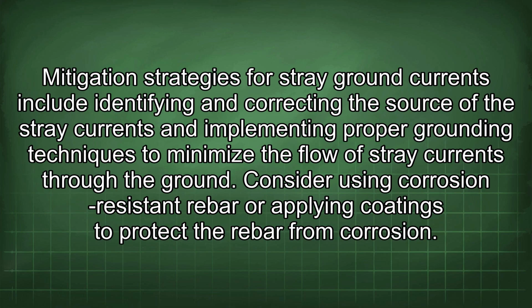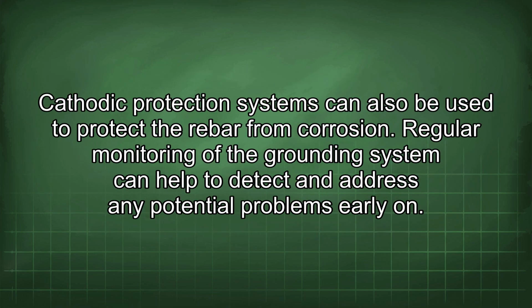Mitigation strategies for stray ground currents include identifying and correcting the source of the stray currents and implementing proper grounding techniques to minimize the flow of stray currents through the ground. Consider using corrosion-resistant rebar or applying coatings to protect the rebar from corrosion. Cathodic protection systems can also be used to protect the rebar from corrosion. Regular monitoring of the grounding system can help to detect and address any potential problems early on.